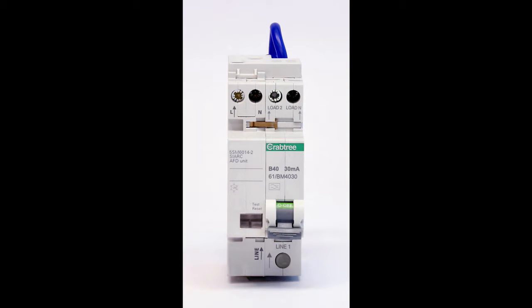By combining Crabtree AFDDs, Arc Fault Detection Devices, with the new miniature RCBO, Residual Current Circuit Breaker with Overcurrent Protection, Crabtree have created a single device capable of providing protection against all the fault conditions as necessary. This device includes MCB technology, RCD technology, and AFDD technology, providing protection against overcurrent, short circuit, earth leakage, and arc fault conditions, all in one DIN-mounted plug-in 2-pole device that also switches the neutral for even higher levels of safety. They also help designers and installers comply with the 18th edition IET wiring regulations.